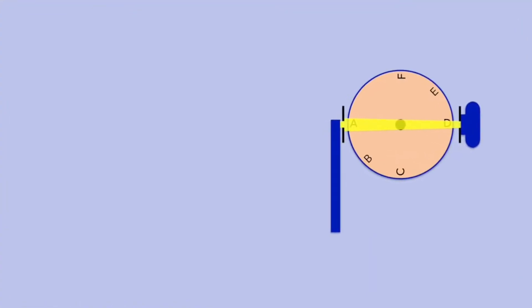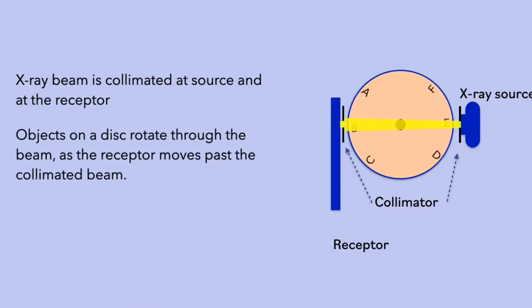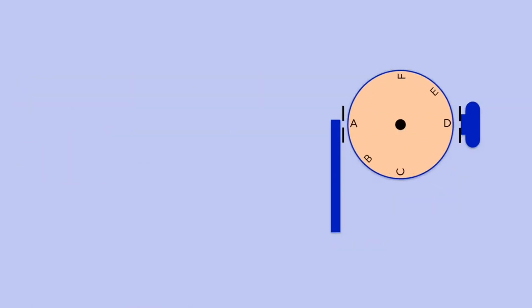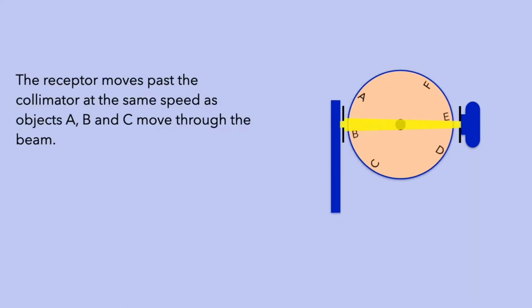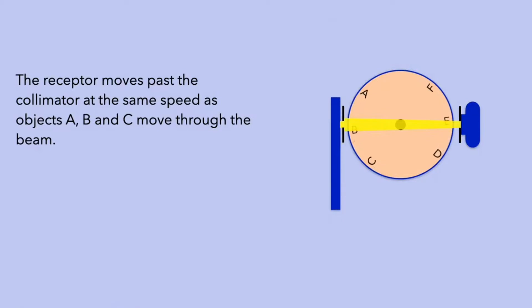To understand the principles of panoramic imaging, let's consider the illustration of a rotating disc. In this setup, X-rays are collimated at the source and immediately before they strike the receptor. Objects on the disc are imaged as they rotate past the collimator. The receptor also moves linearly past the collimator during the exposure cycle. Let's consider the situation where the receptor moves past the collimator at the same speed as objects A, B, and C move through the beam. Images of objects A, B, and C will be recorded when they are closest to the receptor.